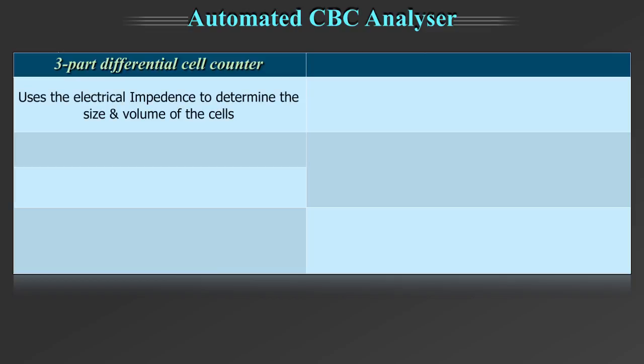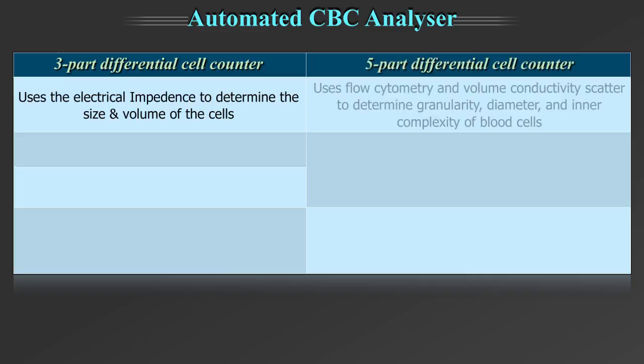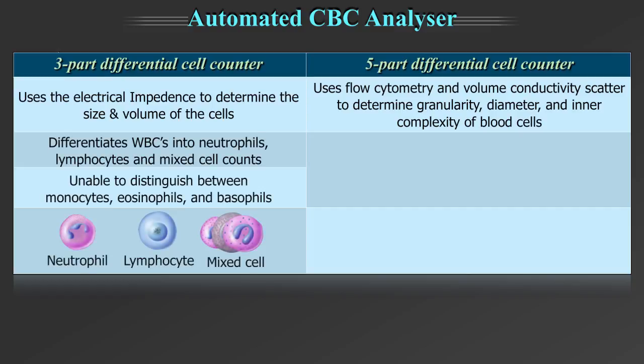Automated CBC Analyzers are of two types based on the type of differential white cell count: the 3-part differential cell counter and the 5-part differential cell counter. The 3-part differential cell counter functions on the principle of electrical impedance to determine the size and volume of the cells. A 3-part differential cell counter differentiates white blood cells into neutrophils, lymphocytes, and the mixed cell count, but is unable to distinguish between monocytes, eosinophils, and basophils.